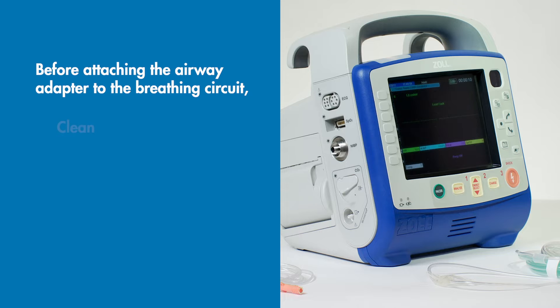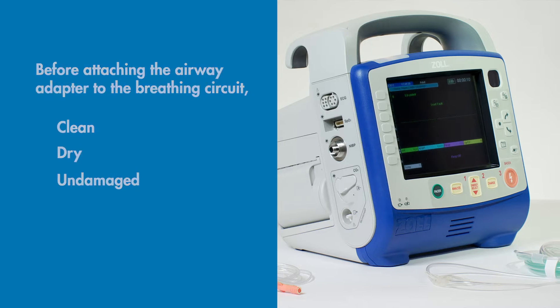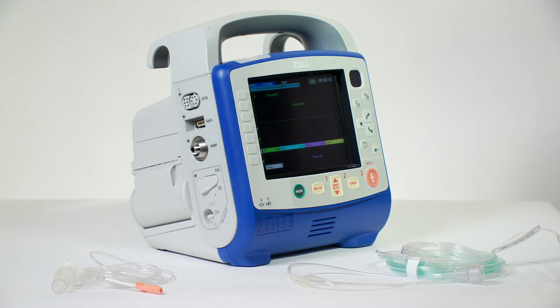verify that the adapter is clean, dry, and undamaged. Replace if necessary. The sensor generates infrared light and beams it through the sample breathing gases, and determines CO2 concentration by measuring the amount of light absorbed by the gases.